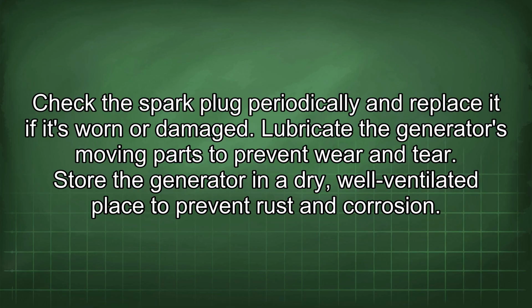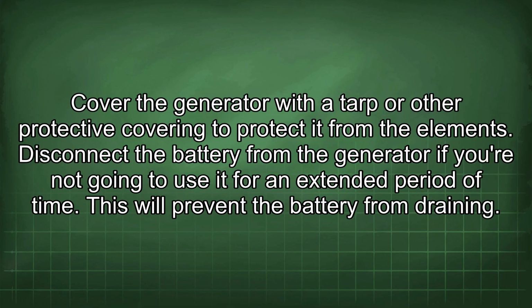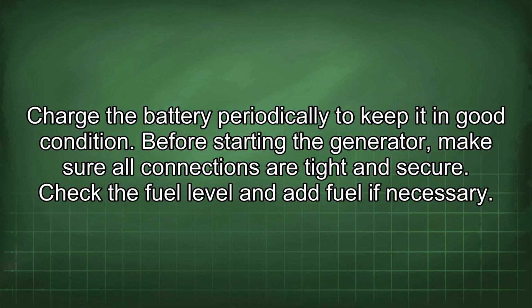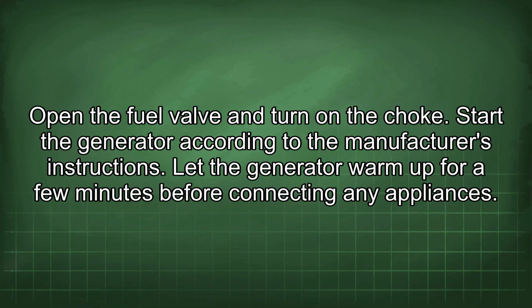Store the generator in a dry, well-ventilated place to prevent rust and corrosion. Cover the generator with a tarp or other protective covering to protect it from the elements. Disconnect the battery from the generator if you're not going to use it for an extended period of time. This will prevent the battery from draining. Charge the battery periodically to keep it in good condition. Before starting the generator, make sure all connections are tight and secure. Check the fuel level and add fuel if necessary. Open the fuel valve and turn on the choke. Start the generator according to the manufacturer's instructions.